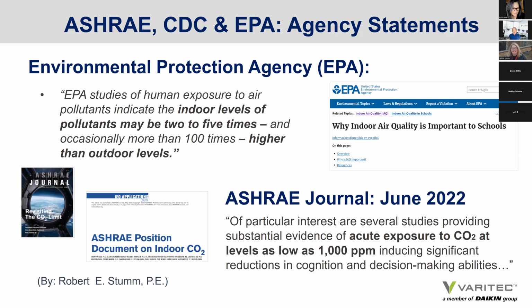Well, that begs the question, do we want to bring in a lot of outside air into a building, especially if you're living or working in downtown Phoenix, and we have the air pollution that we have and cold winter mornings and whatever? Well, I found this statement by the EPA rather interesting. The EPA studies have shown that human exposure to air pollutants indicate that indoor levels of pollutants may be 2 to 5 times, up to 100 times greater than the outdoor air levels. So that's an interesting observation.